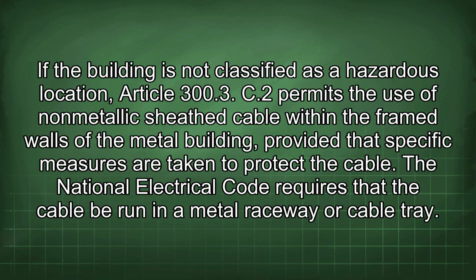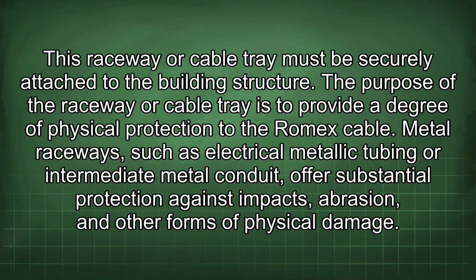If the building is not classified as a hazardous location, Article 300.3 C2 permits the use of non-metallic sheathed cable within the framed walls of the metal building, provided that specific measures are taken to protect the cable. The National Electrical Code requires that the cable be run in a metal raceway or cable tray. This raceway or cable tray must be securely attached to the building structure. The purpose of the raceway or cable tray is to provide a degree of physical protection to the Romex cable.